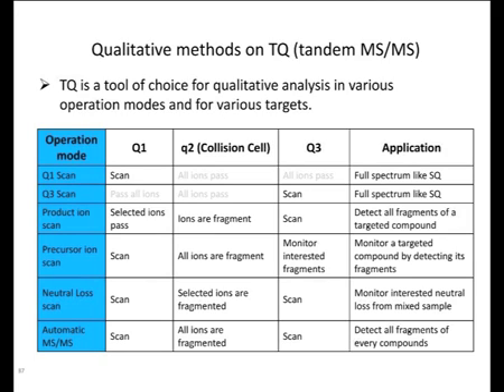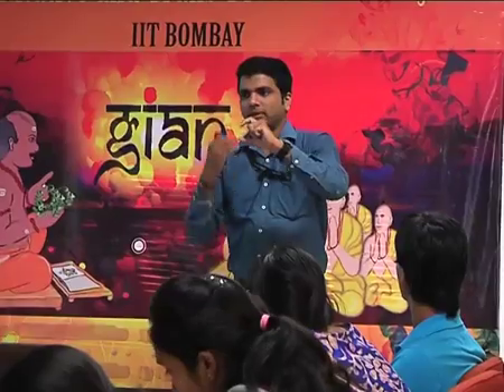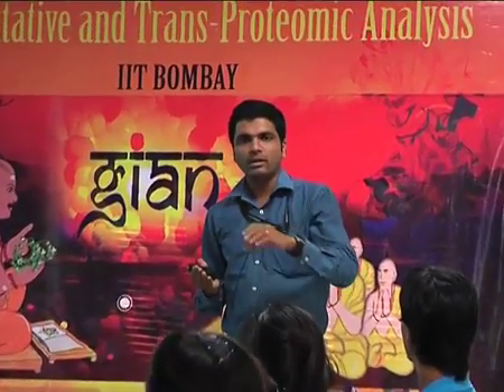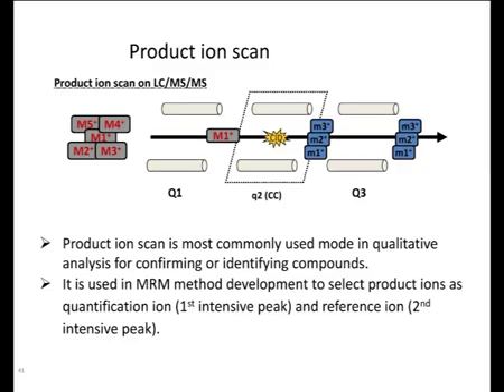I am not going to discuss them in detail. Most important is MSMS, that is MRM, multiple reaction monitoring. Here, the first quadrupole is in the SIM mode, selecting the particular precursor ion. It passes to the second quadrupole, where it is fragmented and forms different product ions. Among all the product ions, you select the product ion that is specific to your compound of interest and has good intensity. The third quadrupole is also in the SIM mode. This precursor-to-product pair is known as the MRM transition, and it is used for quantitative analysis of the compound from different matrices.